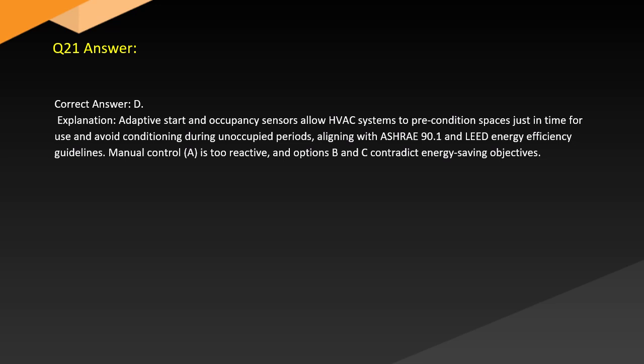Answer. Correct answer: D. Explanation. Adaptive start and occupancy sensors allow HVAC systems to precondition spaces just in time for use and avoid conditioning during unoccupied periods, aligning with ASHRAE 90.1 and LEED energy efficiency guidelines. Manual control, option A, is too reactive, and options B and C contradict energy-saving objectives.